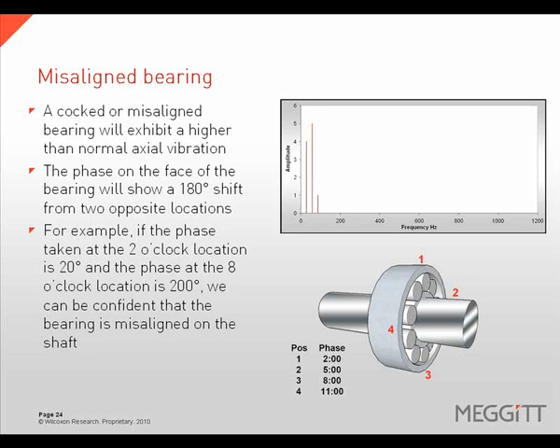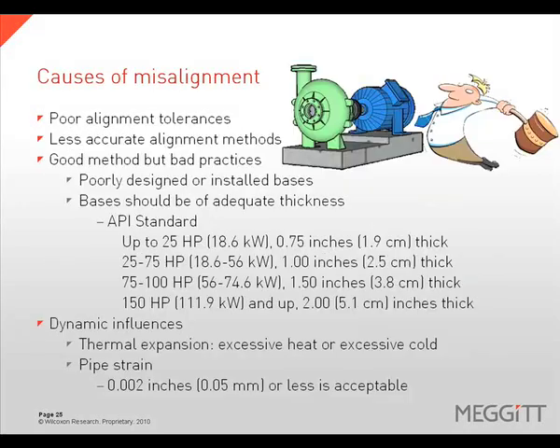The phase shift can be at any two locations around the face of the bearing that are 180 degrees apart. There are many causes of misalignment, including poor alignment tolerances, less accurate methods such as a straight edge, poorly designed bases, and dynamic influences like thermal growth or pipe strain.